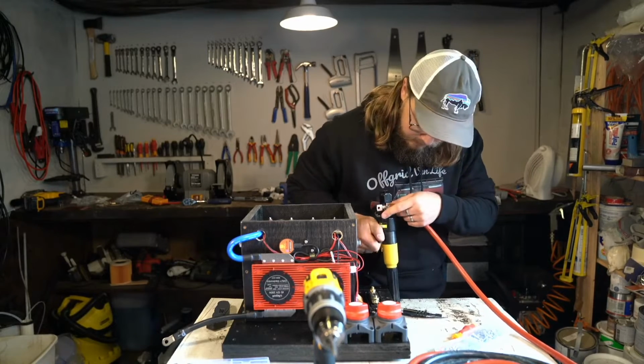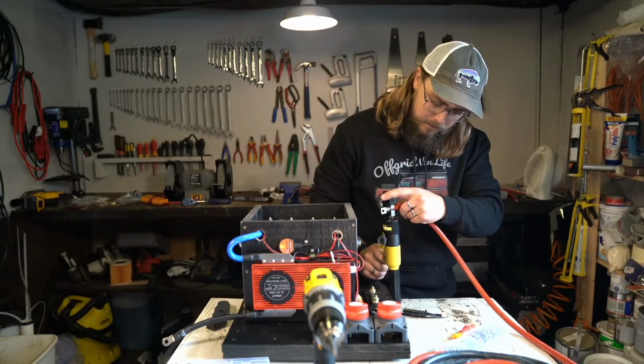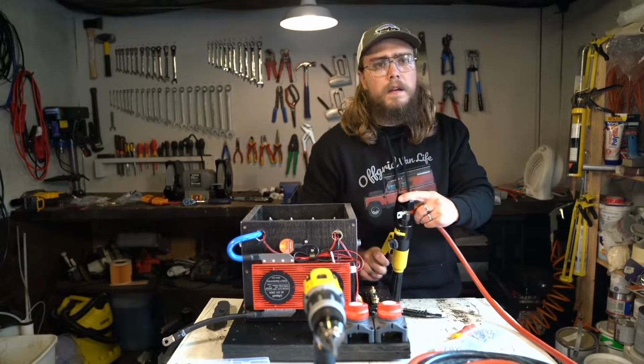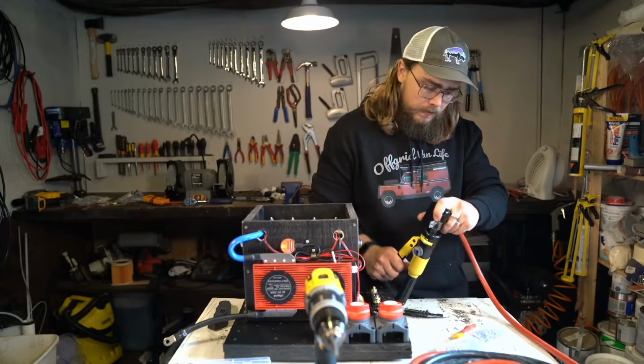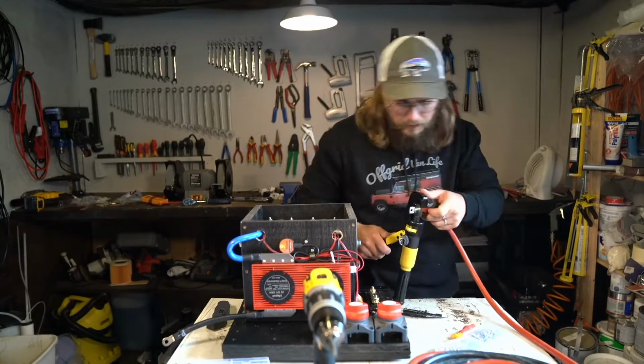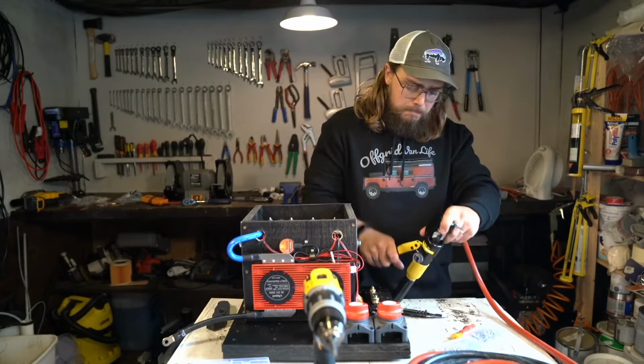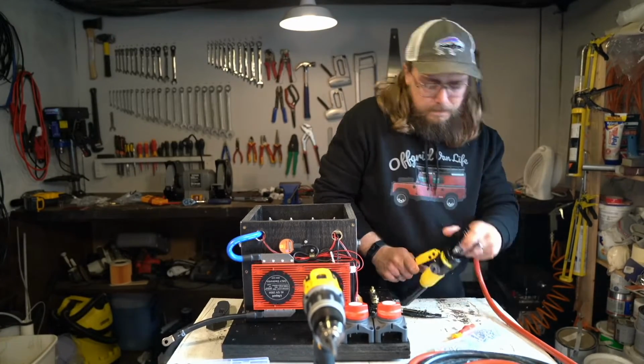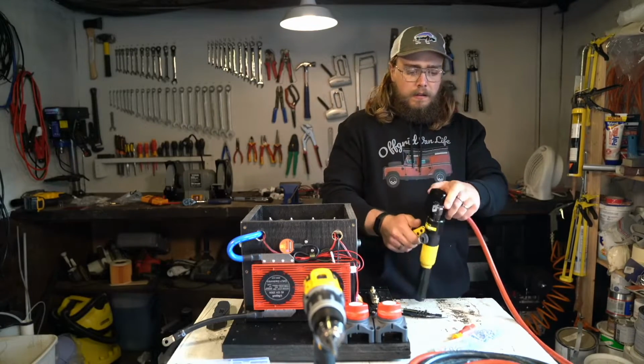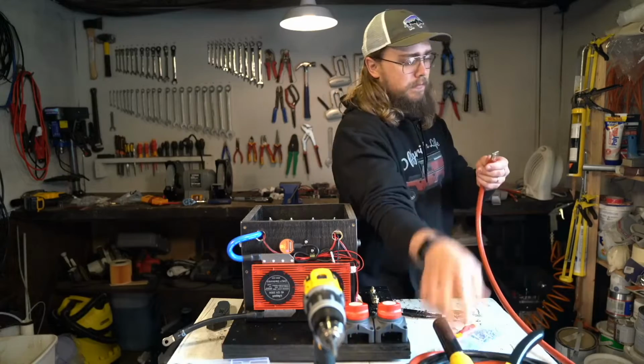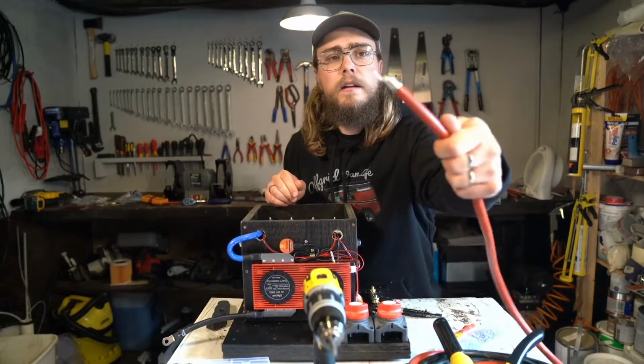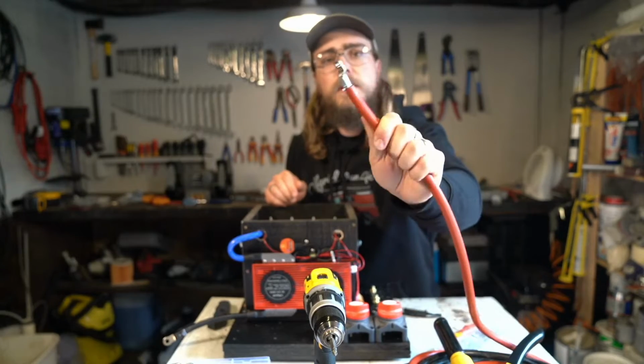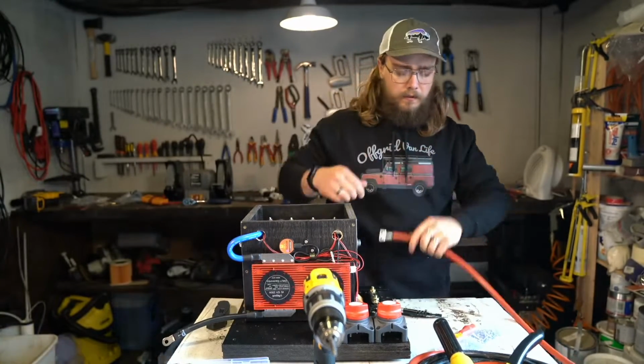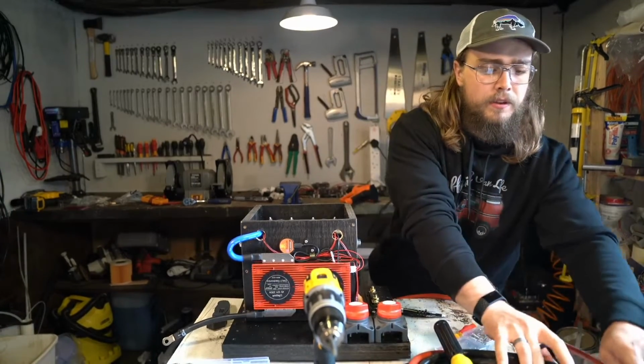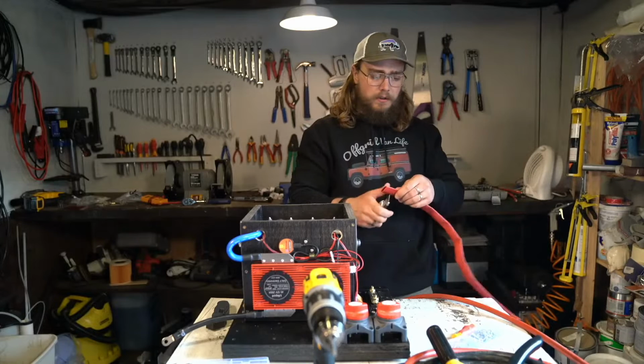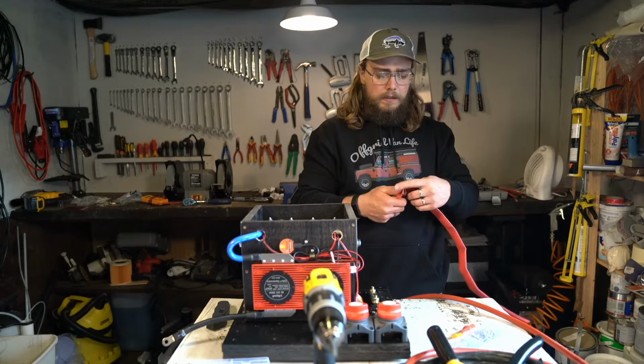I'll do it all the way up to the end of the lug, right against the insulation on the cable. This thing's twisted here a bit. Alright, release that, and there we go. Look at that, that's a nice crimp on there. Give it a bit of a tug test, and I'm pretty happy with that crimp. So that's what you'd call a cold weld.